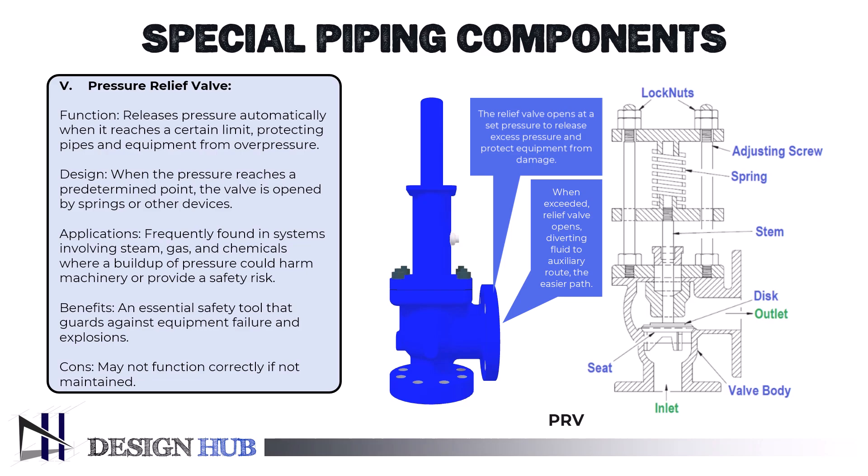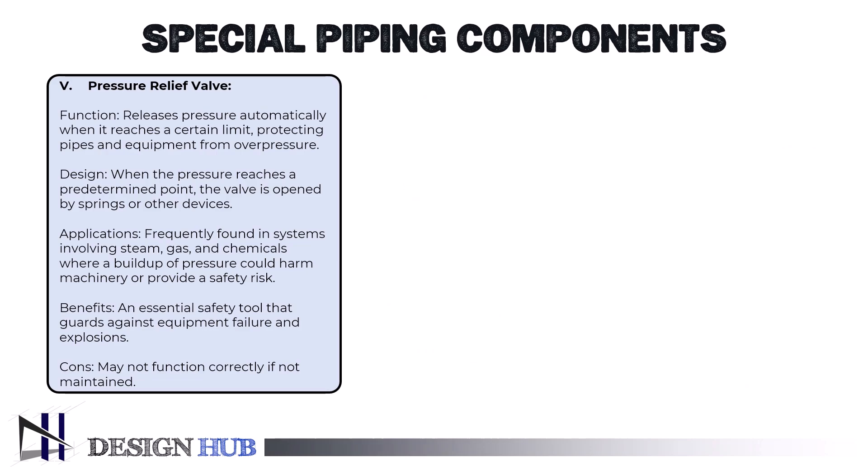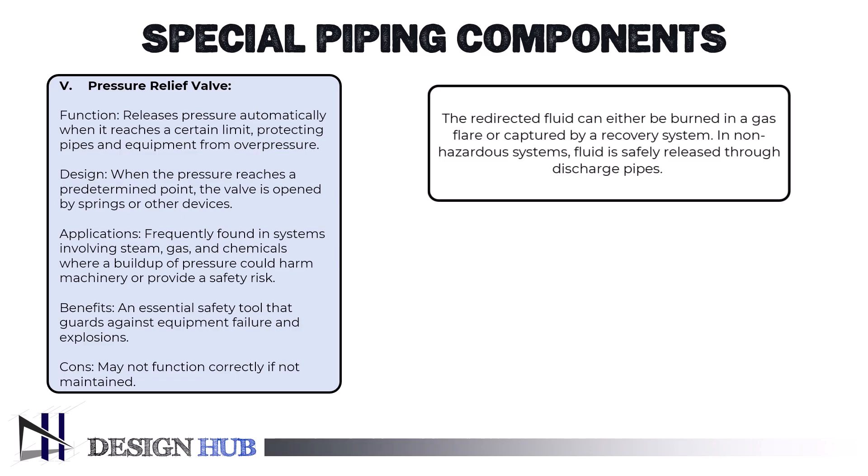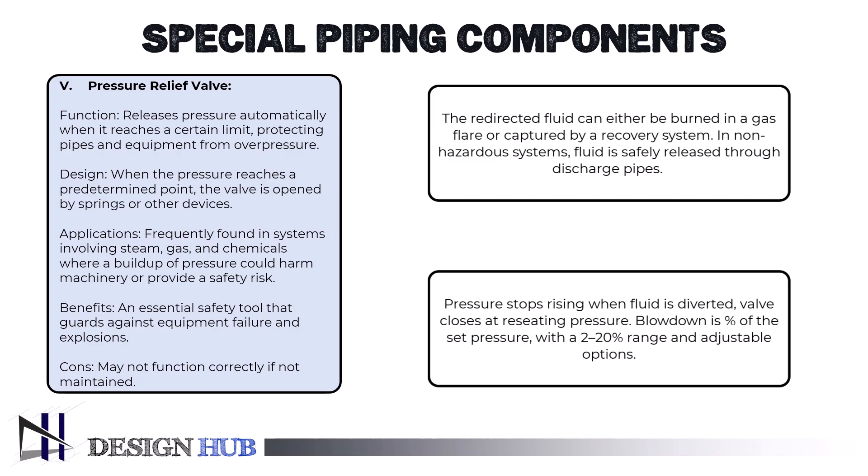As the relief valve is forced open and some fluid is redirected into the auxiliary route, it becomes the path of least resistance when the set pressure is surpassed. In systems containing combustible fluids, the diverted fluid — liquid, gas, or liquid-gas mixture — is either sent to a central elevated gas flare where it is burned, or captured by a low-pressure, high-flow vapor recovery system. In non-hazardous systems, fluid is often released into the atmosphere via appropriate discharge pipework positioned so as not to endanger personnel and prevent rainwater penetration, which can alter the set lift pressure.